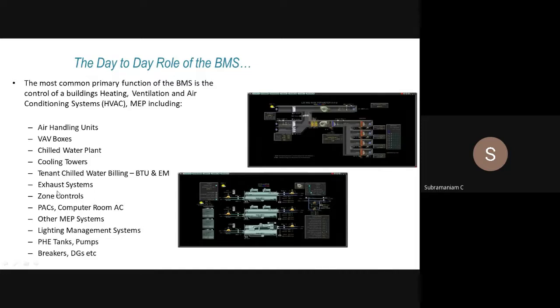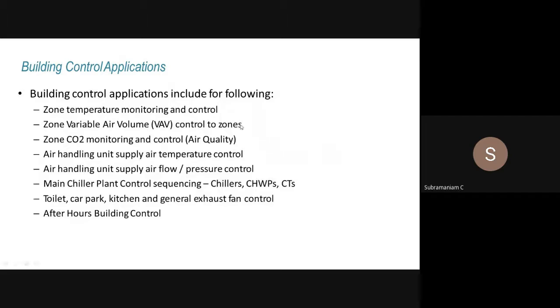Which means if we have 20 exhaust fans, 5 cooling towers, 400 VAV boxes in a building, precision air conditioners, and lighting management systems, if we start building from unit level, then system level and top level, we can make the functioning of all this automated. It will also do zone temperature monitoring and control, zone VAV control, zone CO2 monitoring and control, demand control ventilation, which we'll see, air handling unit supply air temperature control, chiller plant sequencing, and toilet, car park, kitchen, and general exhaust control. All that it will do.